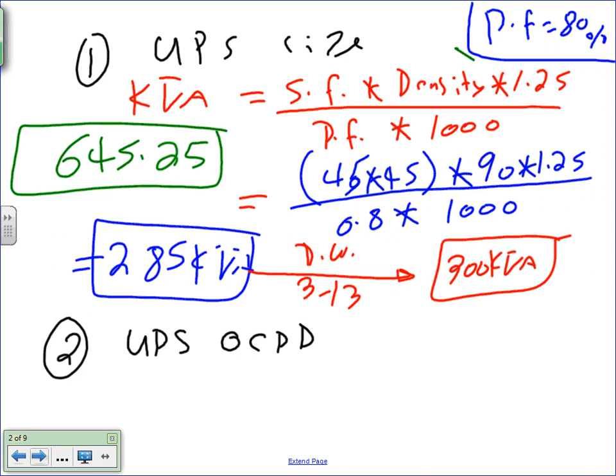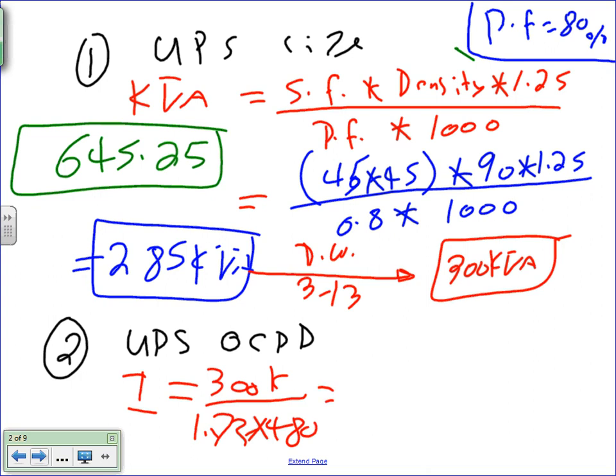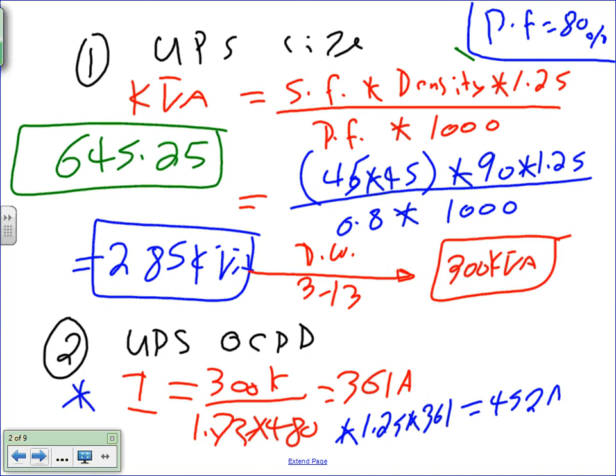The UPS overcurrent protection device, my friend. This becomes a piece of cake. You take the I. Now we need to calculate the current. 300K divided by the voltage, which is 1.73 times 480 because of three phase. If you go there, we'll get 361 amps. And then I need to multiply this as a continuous load. So that's step 1. I want to treat it as a continuous load and take 1.25 multiplied by 361, and that will get me a continuous load of 452 amps.